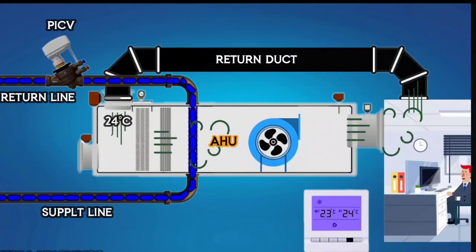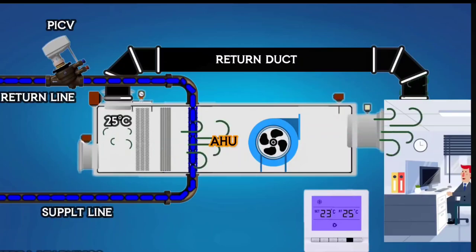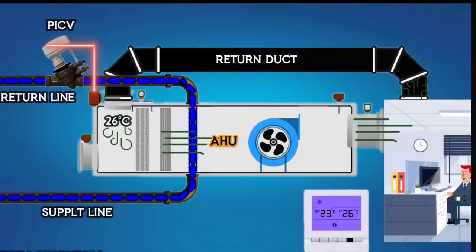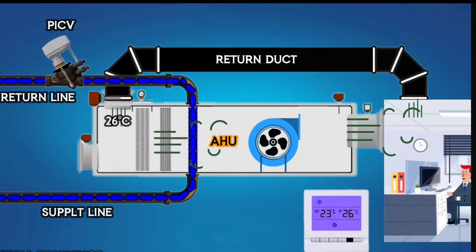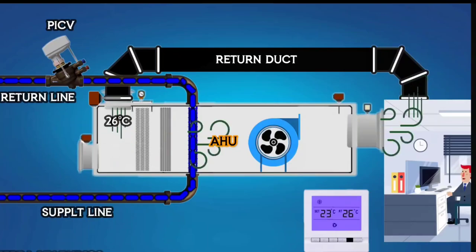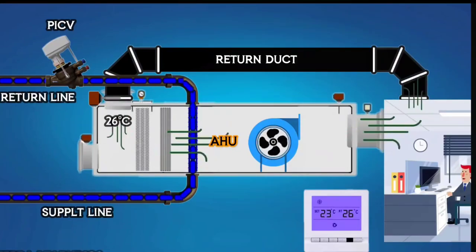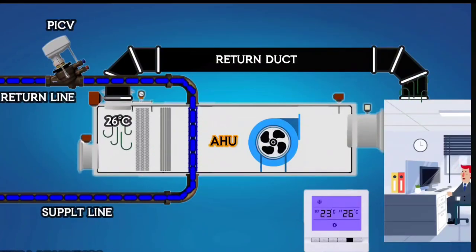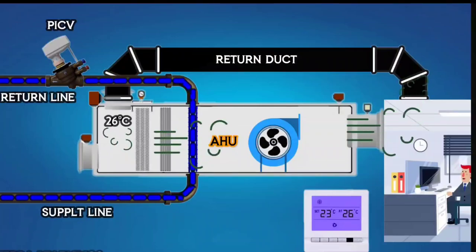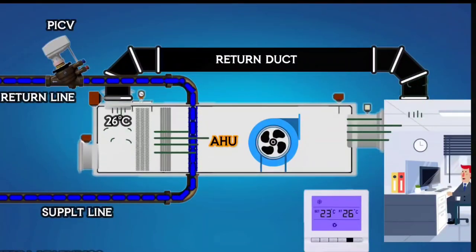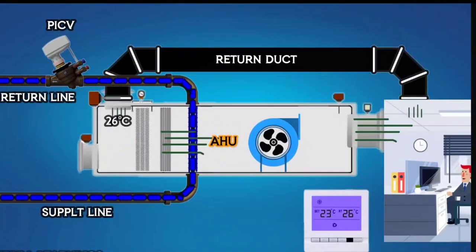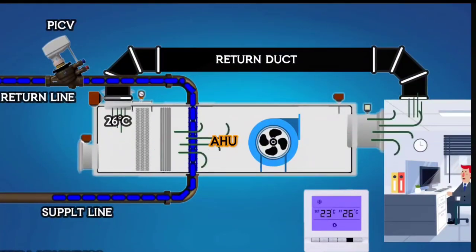When the room temperature exceeds the set point, the temperature sensor again sends a command to the actuator to open the valve. Then again, the water starts to flow inside the AHU. This same process happens in all AC units, like AHU, FCU, and BCU. This is how PICV works.